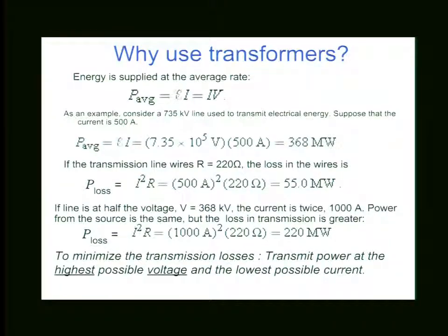Suppose the current is 500 amps. The power is 735 kilovolts at 500 amps—that's the total power put out. But if the transmission line has, say, 220 ohms resistance, the loss in the wires is that current, 500 amps, squared times the resistance, which comes out to 55 megawatts. So out of the 368 megawatts, you might lose around 10% nationwide on average.